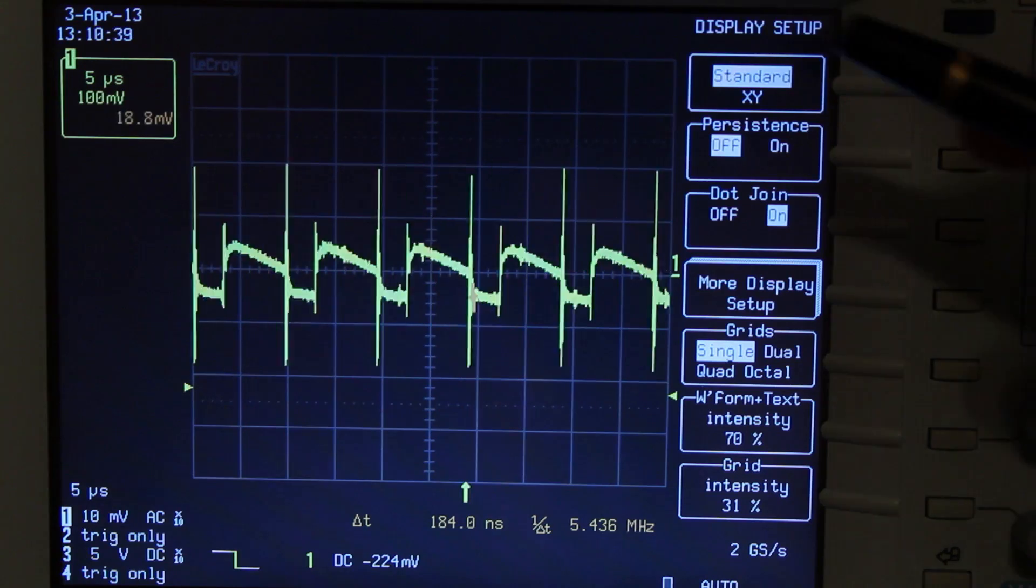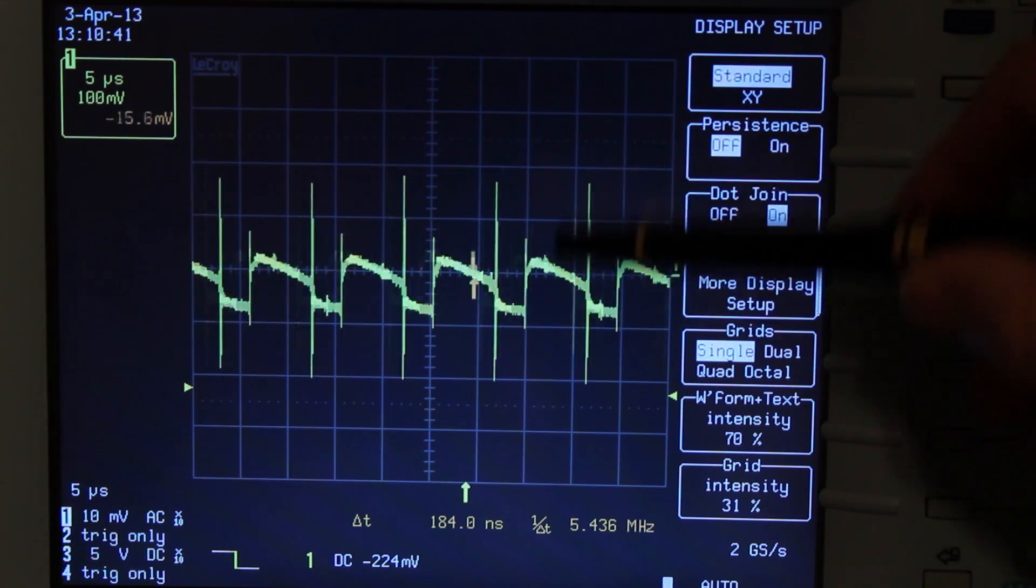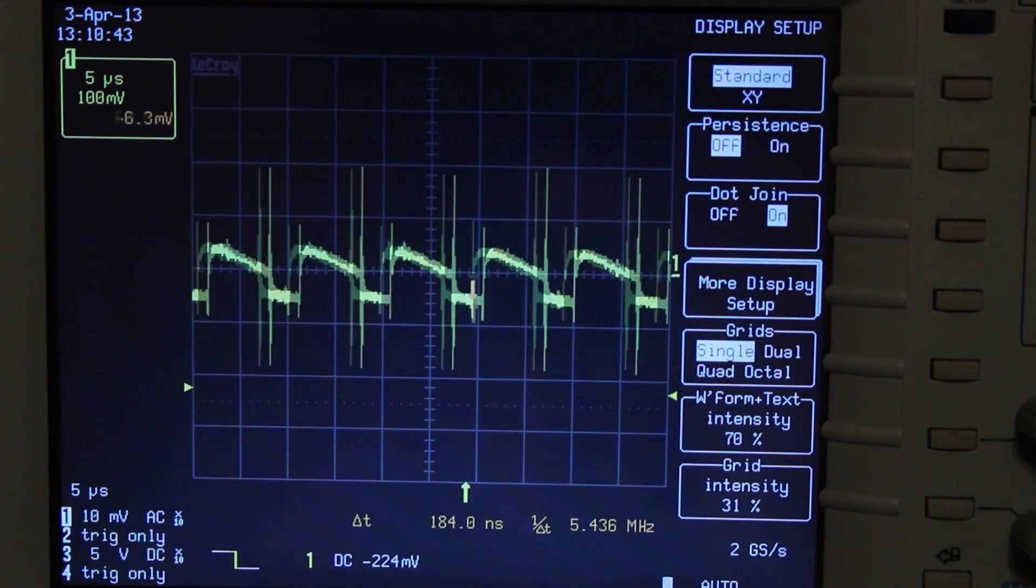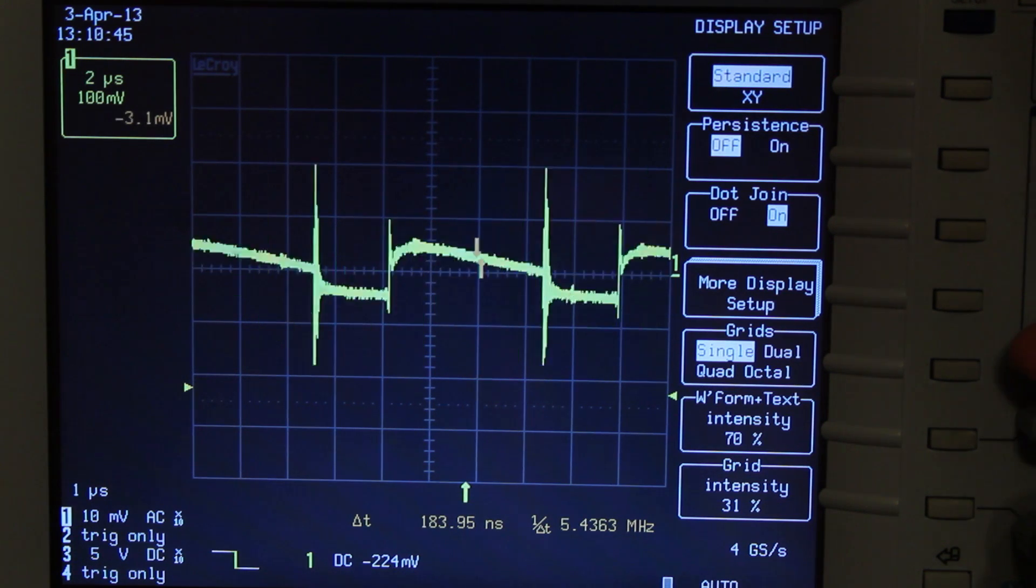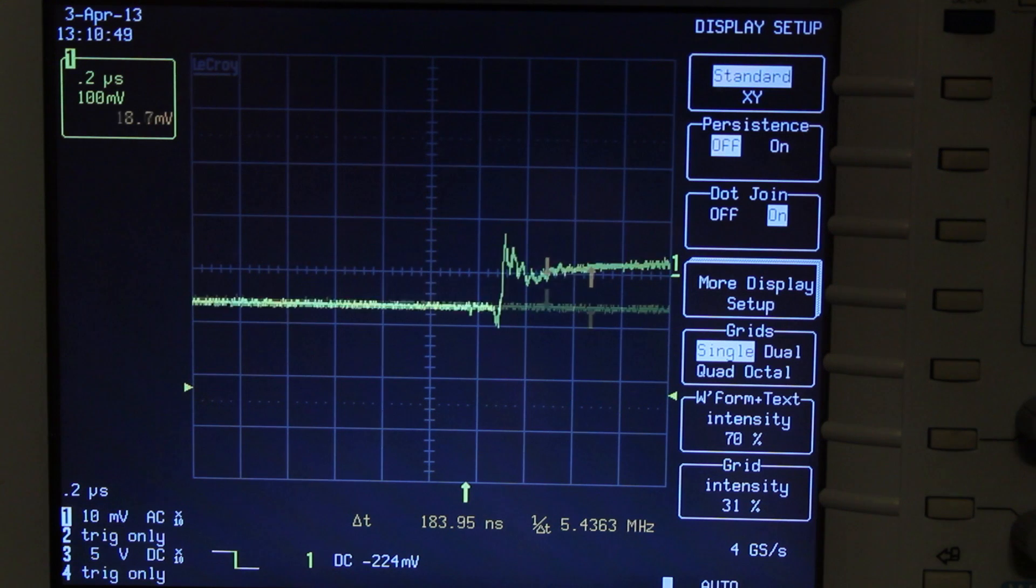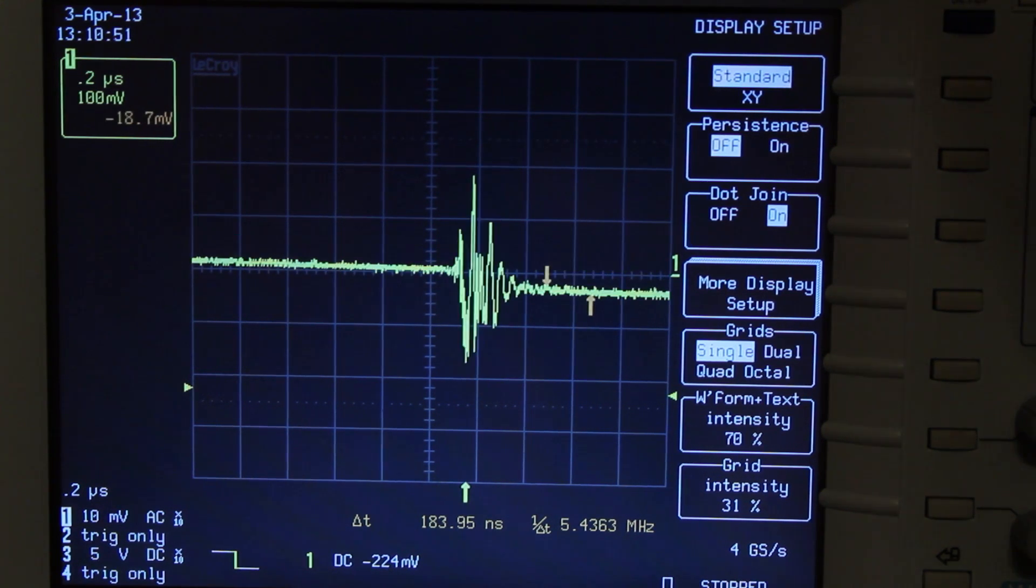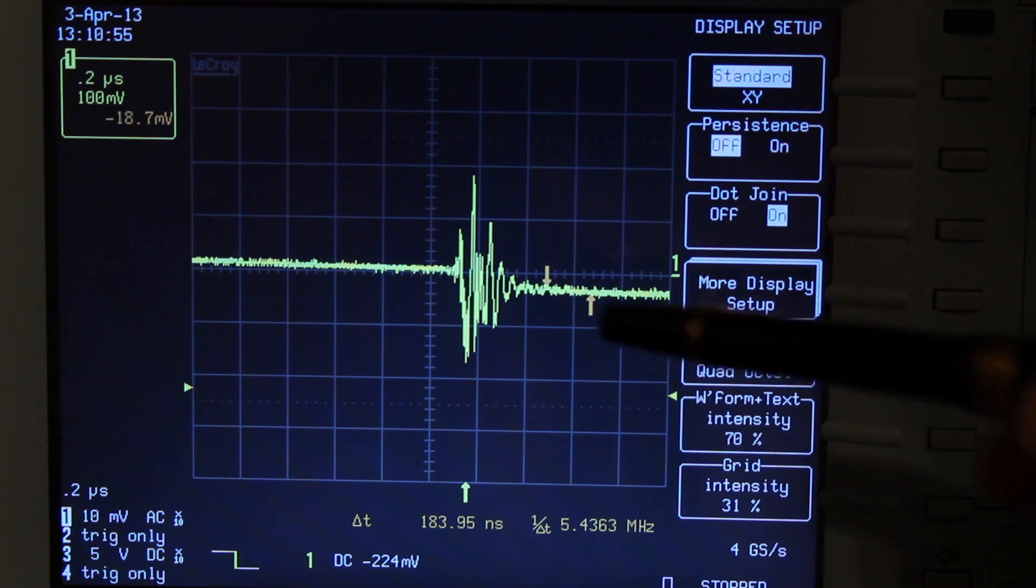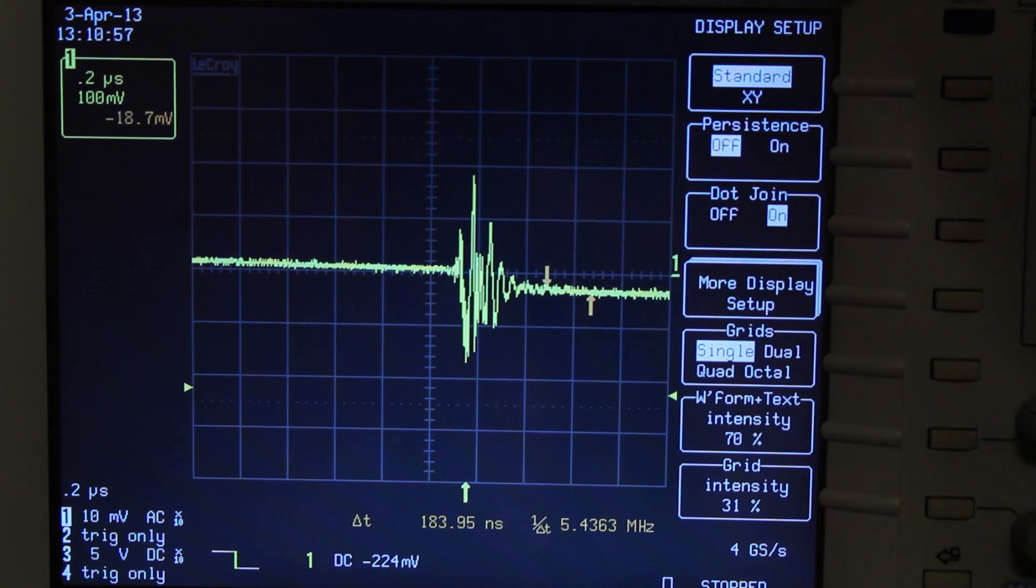But we can see there's still spikes that haven't been resolved at this time base. So let's turn the time base a little bit further. Now we go to 200 nanoseconds per division. And there if we do a single shot capture, we can see the noise that exists at 200 nanoseconds. And that's probably about 20 megahertz noise or more, which is going up to 400 millivolts.